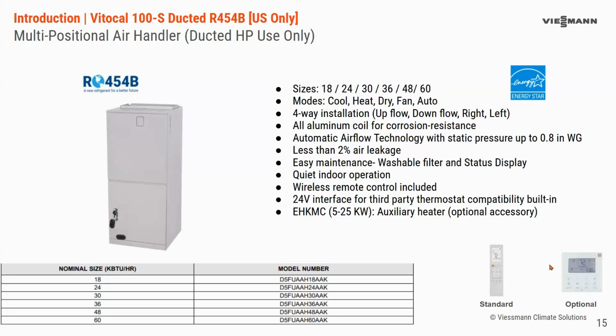Wireless remote is included for this, in the event that you purchase a wired remote or wired controller separately, or just for use with the unit for setting the set point or servicing. The reason that the wired controller is not included with this unit is the 24-volt interface is built into this unit, and this is a central ducted application where we see a lot of the end users putting their own thermostat there. So you can plug a 24-volt thermostat right into this air handler without any additional interfaces. So that's the reason why the wired controller on the ducted is not included, whereas on the ductless, it is included.